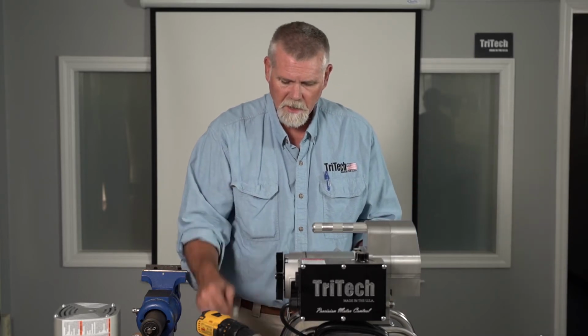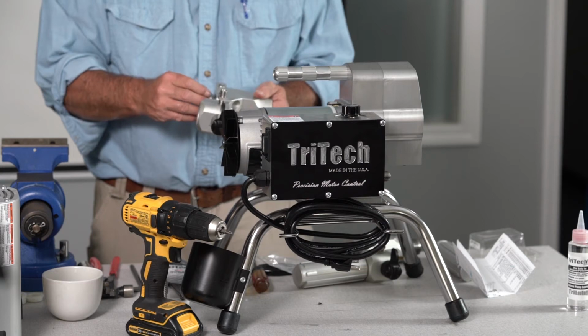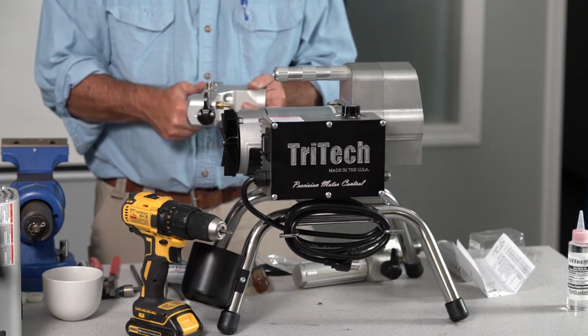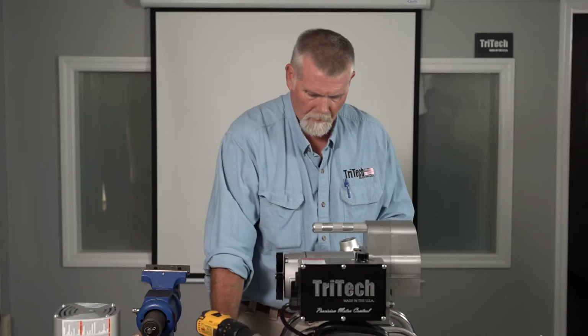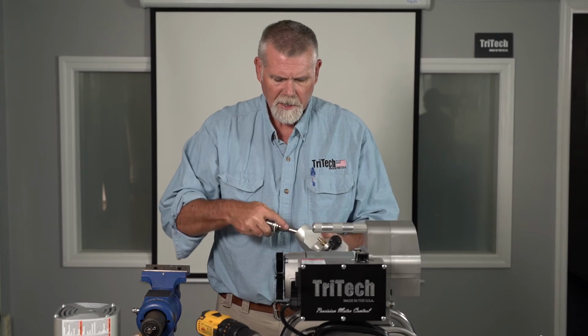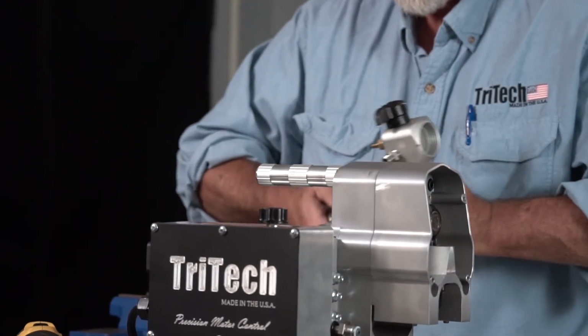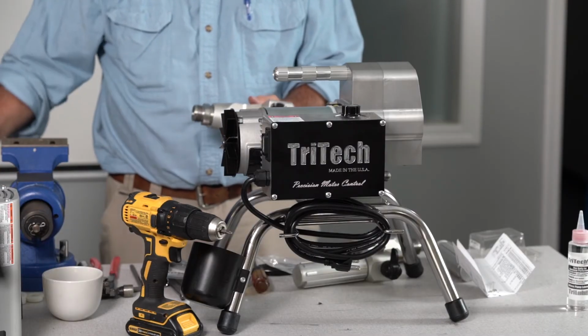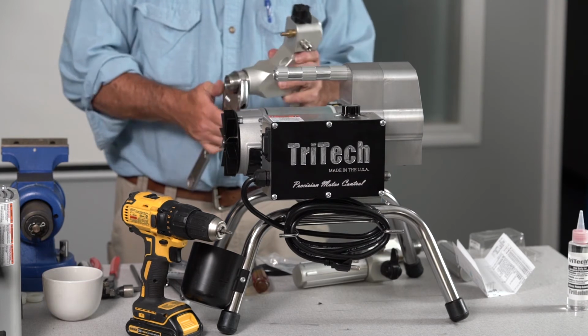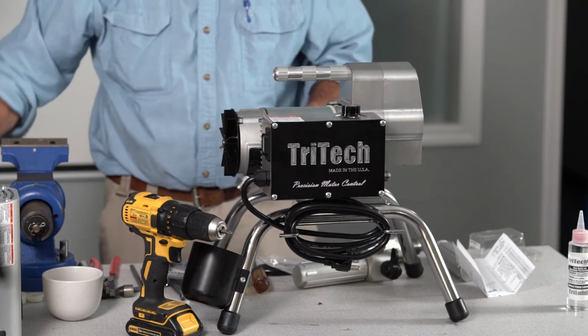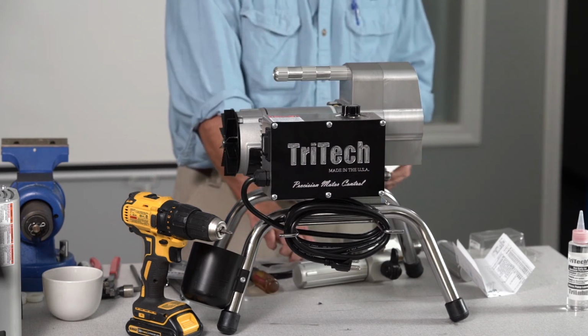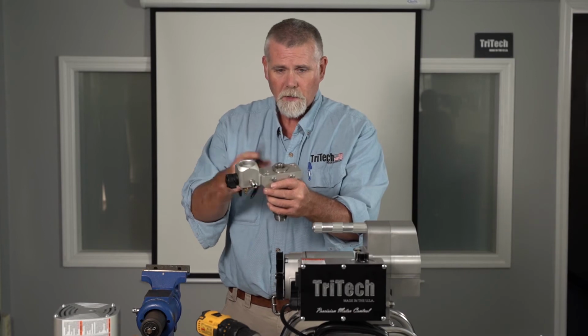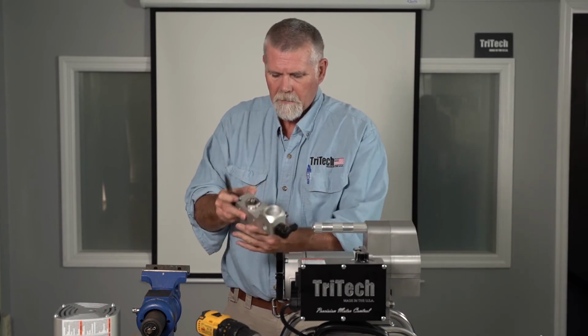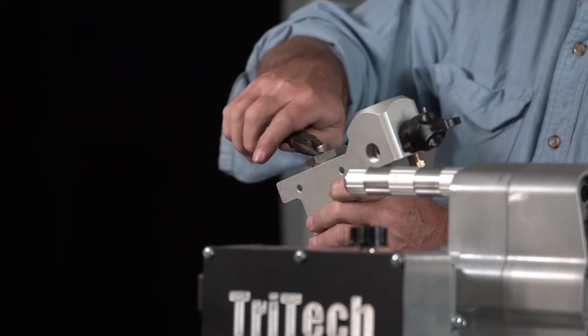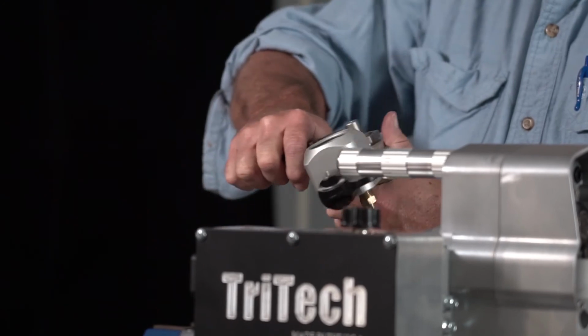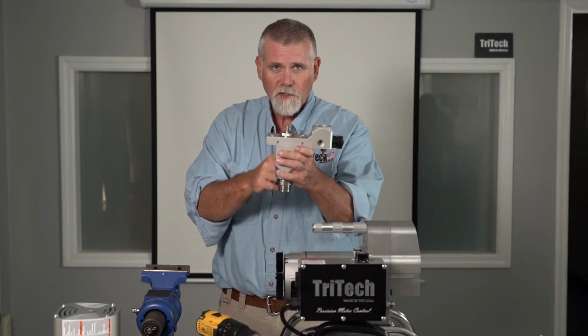You can put your upper piston guide in your upper packing retainer. Thread that in. Then you take your foot valve assembly with your piston in it, insert it into your lower packing. Because the packings are new, you're going to use a tool to thread it the rest of the way in. Once that's in, you can see your piston is up through your upper packing retainer. Just grab a pair of needle nose pliers, pry your piston up, and align the slots front to back.